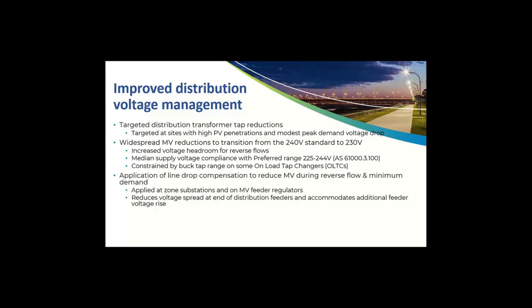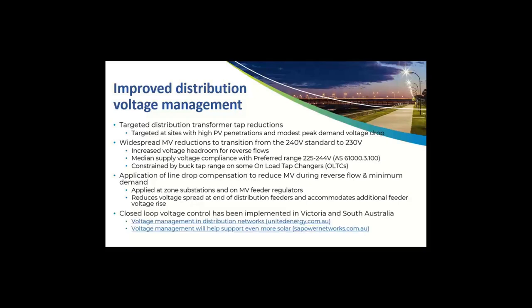We've also implemented increasing amounts of line drop compensation, and that's been used not to boost voltages further during peak demand, but to pull the voltage down during those reverse flows. Once again, this increases the headroom for reverse flows, and also reduces the voltage spread at the ends of distribution feeders.